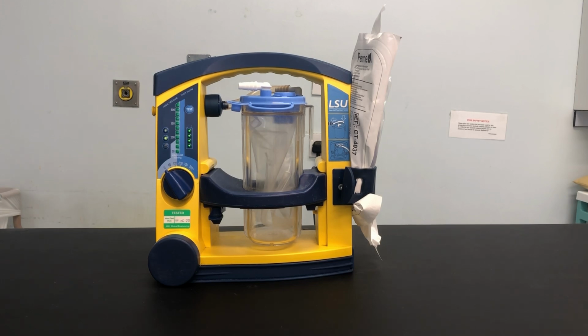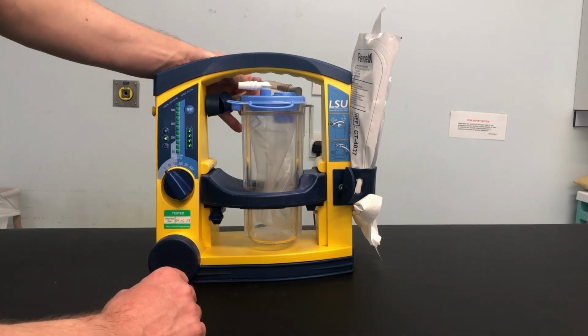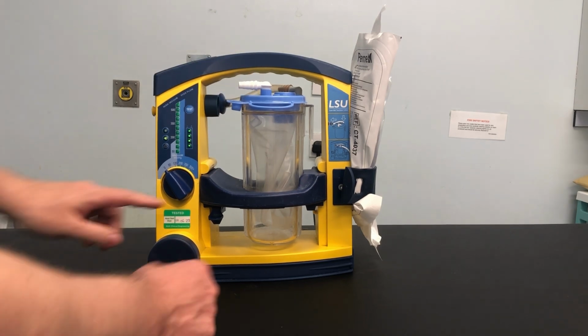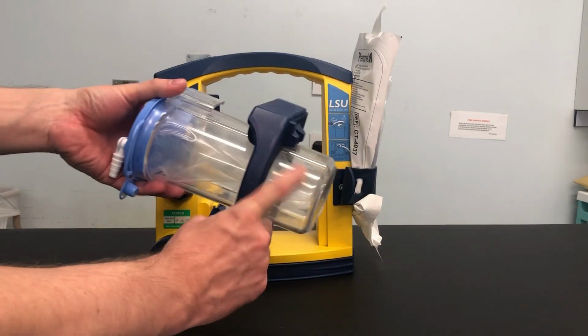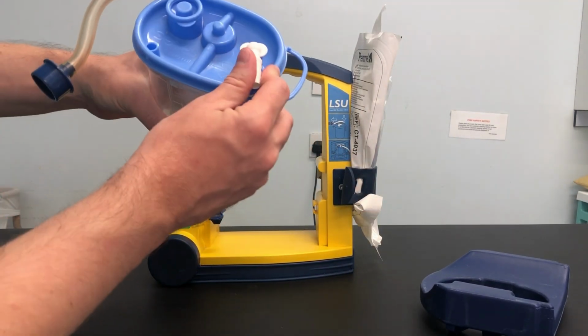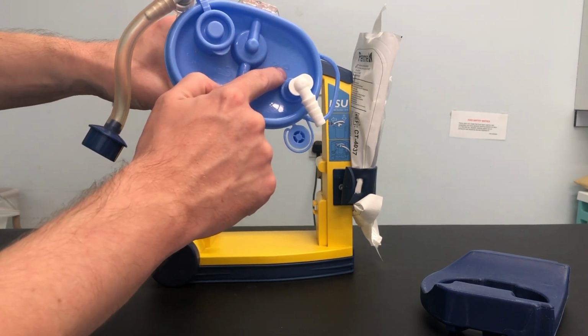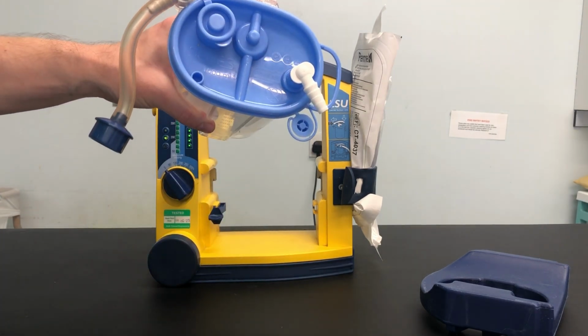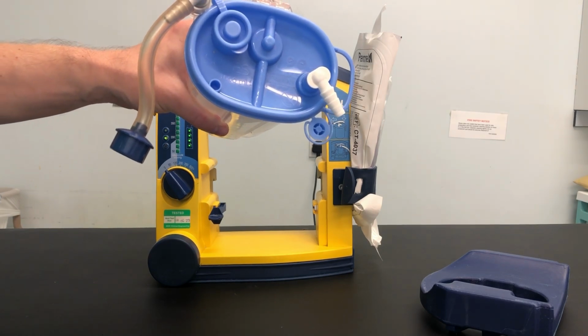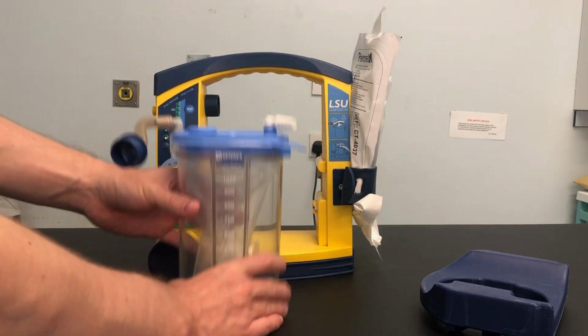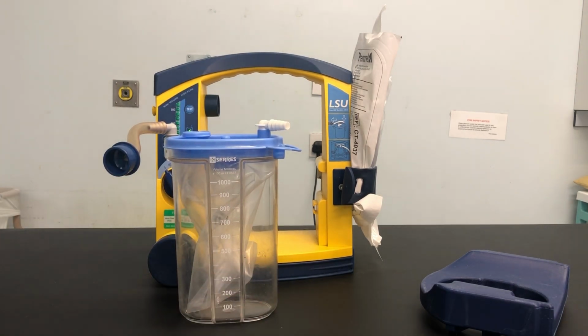So on to assembling the Serres suction liner. Remove and check the canister liner on a regular basis for signs of damage. Remove and replace if the canister liner has expired. There are 2 dials on the top of the lid, one indicating a month and the other indicating the year. This is the date of manufacture, and the canister liner will expire 5 years after the date of manufacture. Please note that apart from the packaging, this is the only indication of dates, and the numbers printed on the side of the liner are not a date of manufacture or expiry.